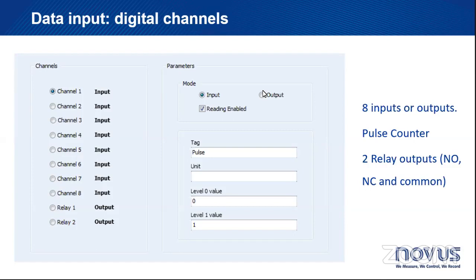So alarms can be triggered by those outputs. So for example, I could reset some counting with a button that is linked to a digital input. But also, and that's very, very powerful about the FieldLogger, digital inputs can read pulses. And by reading pulses, it allows you to connect it to flow transmitters that generate pulse output. So voltage pulses. And the FieldLogger will count those pulses and totalize volume or find out the flow rate. So that is a very important function that will allow you to do several other applications, okay?